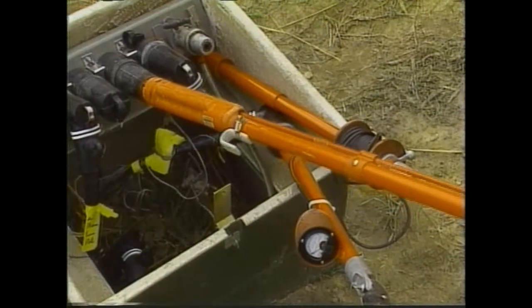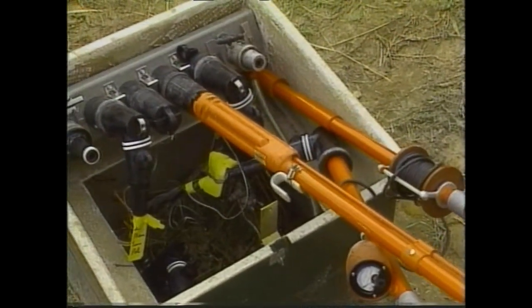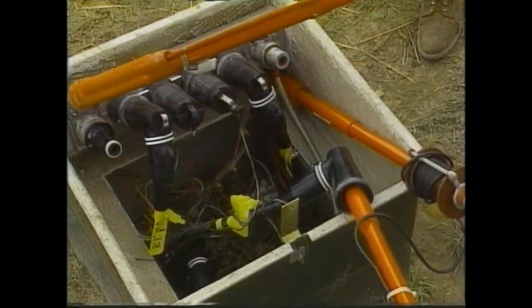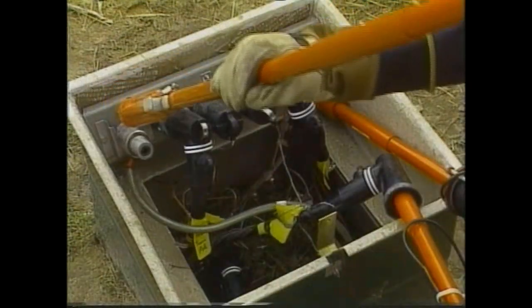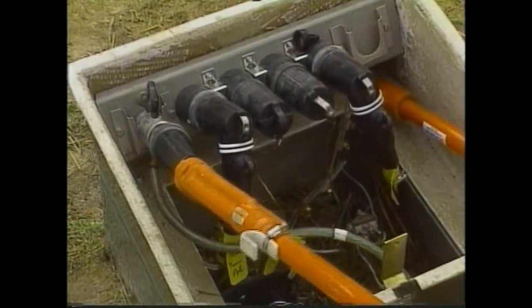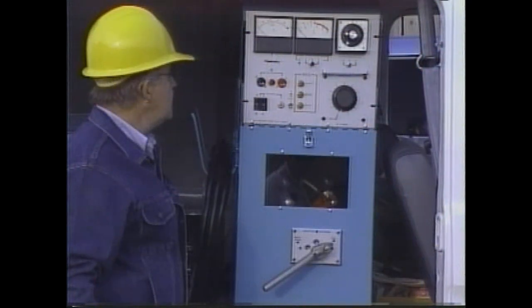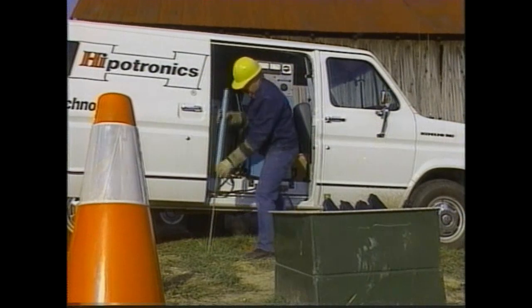Having identified the problem cable, we install the protective cap. And ground this end of the cable. With the cable isolated and grounded, we are ready to set up the thumper. And at every stage in the process, we check everything we've done so far to make sure the work is safe, correct, and complete before moving to the next step. We check to make sure all of the thumper controls are off and the function control is in the ground position. Now we are ready to set up all of the necessary grounding. The thumper operator installs a driven ground rod for the vehicle his thumper is mounted in.